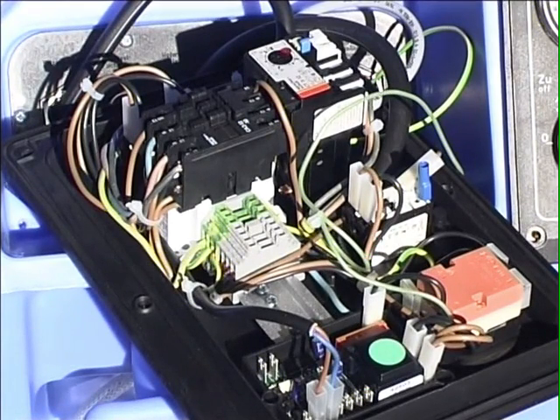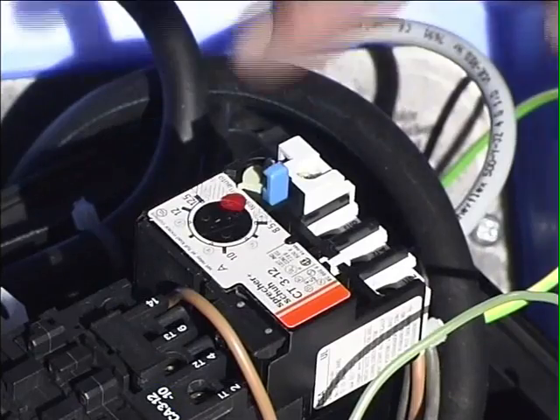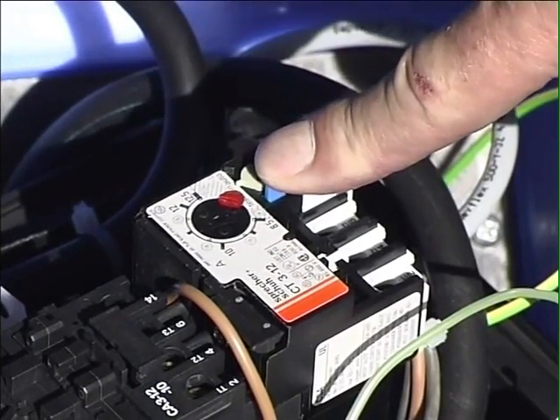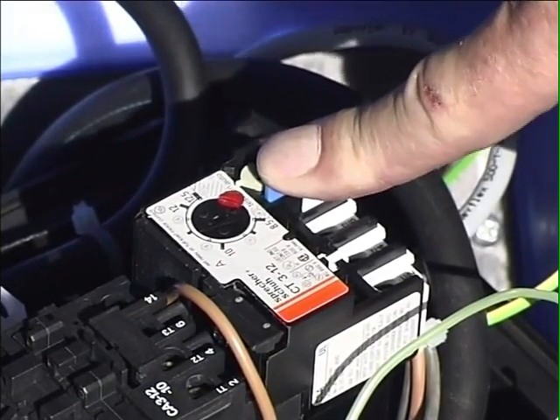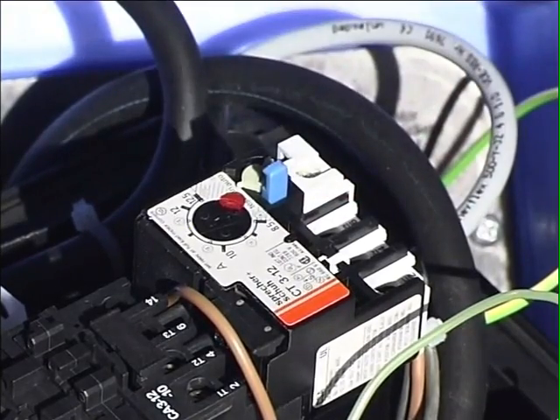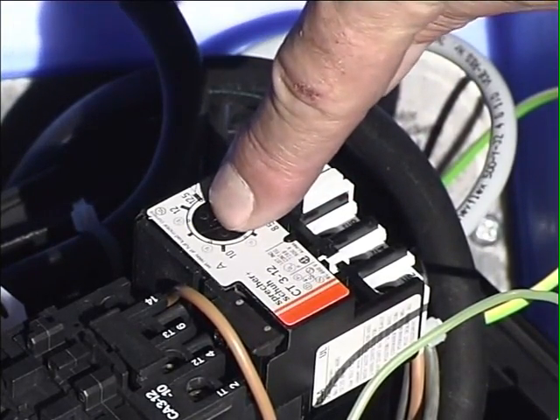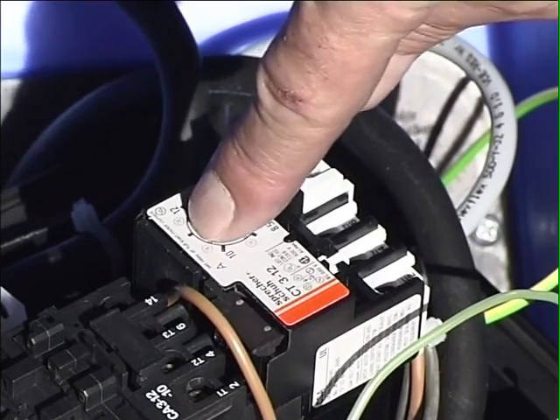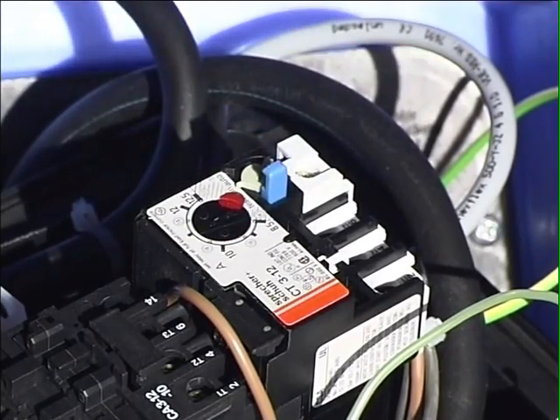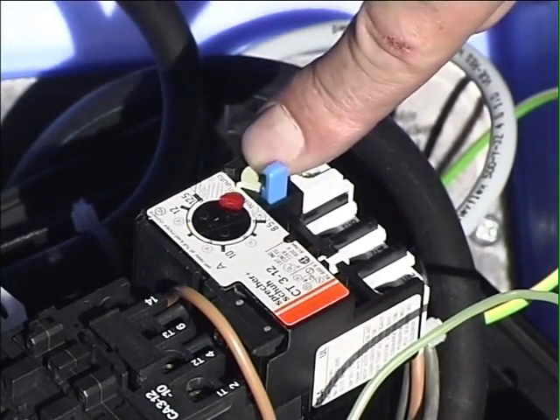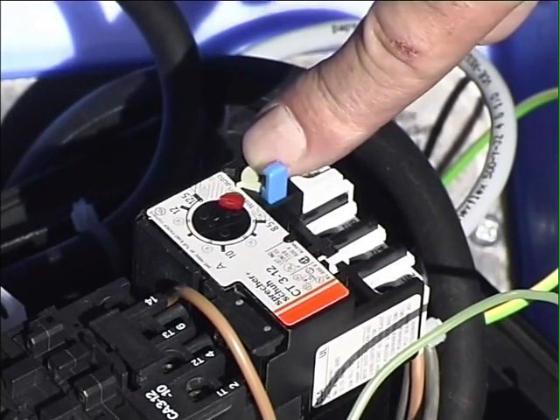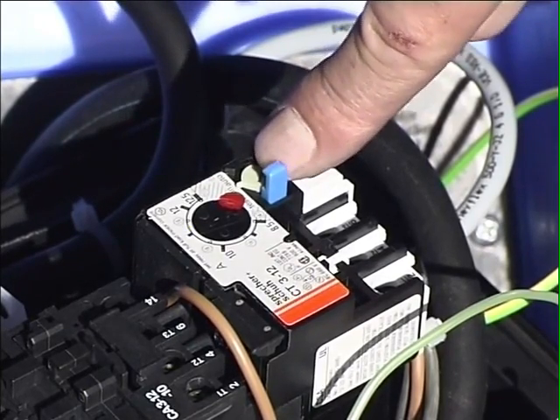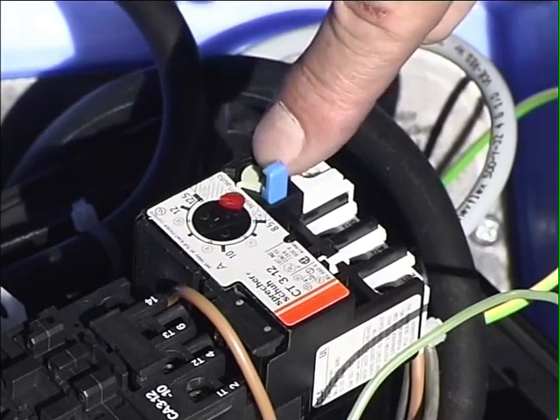The next possibility. The voltage is too low, triggering the motor protection switch. It is placed in the initial position. Determine whether the ampere number has been correctly set for the machine and whether the voltage is correct. The correct position of the motor protection switch is automatic. The motor protection switch can be defective. In this case, it must be replaced.